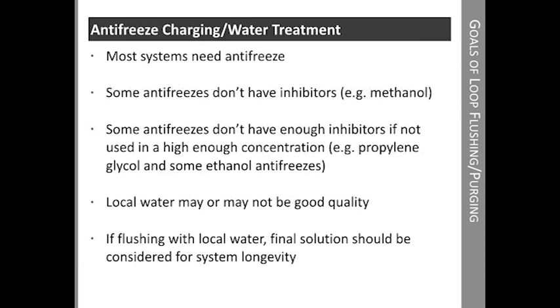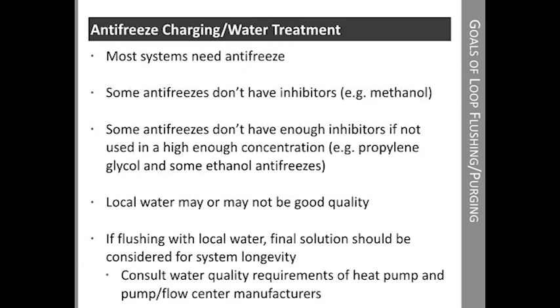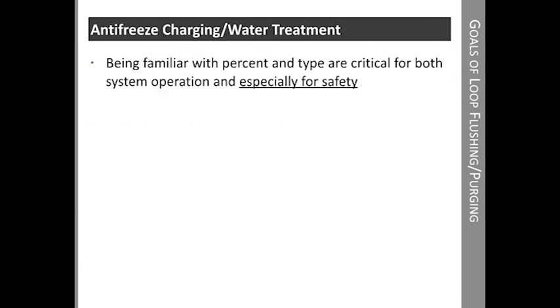In southern areas where antifreeze is not used, an inhibitor should be added. It is a good idea to verify water quality requirements from the heat pump manufacturer and flow center or pump manufacturer since it could affect warranty. The percentage of antifreeze and the type are critical for both system operation and especially for safety. Let's look at the most common geothermal antifreeze solutions.